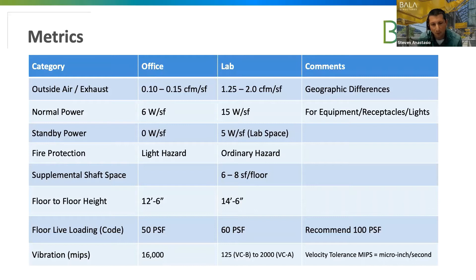And so if we're dealing with code minimums, how we make up the difference is there's a partition allowance of 15 pounds a square foot that we can pull from to get the floor up to par without having to reinforce it. And for vibrations, this gives you an idea of the difference between an office requirement and if you want to go for a VC-A, which is the minimum vibration requirement for a lab. VC-A pretty much handles bench microscopes and items like that, but it's almost a factor of 6, or sorry, 8 between the two. So if you need that vibration performance over the whole floor, it can add a significant amount of cost to upgrade it. So what we've seen is we'll look at the equipment that's actually going in the space and locally reinforce the floor at those areas.